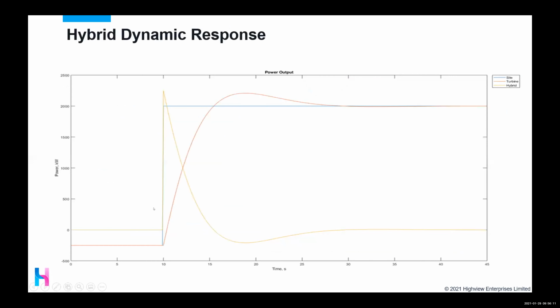So this is a graph to show you what we were trying to do with this hybrid dynamic system. Your orange trend here is the system motoring in spin gen mode. You can see we're at a negative load of about minus 300 kilowatts, motoring along, absorbing power from the grid in a readiness state. We get called to operate and we ramp up the turbine to nominal power. So we overshoot and then we settle down at the two megs in this case.